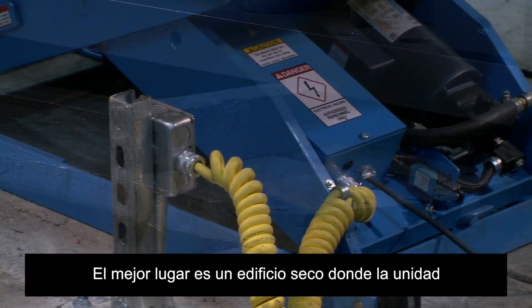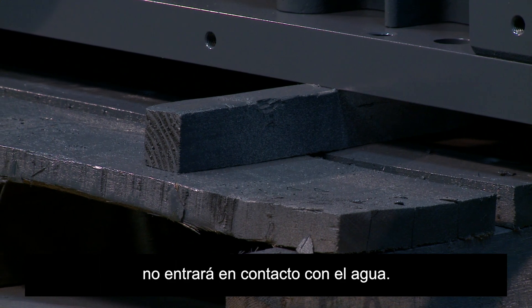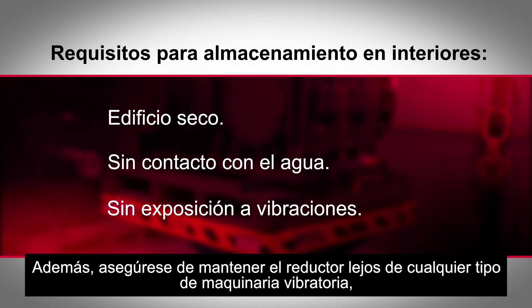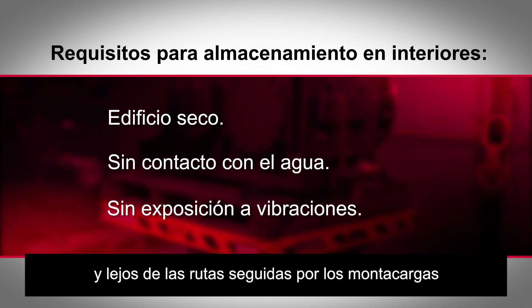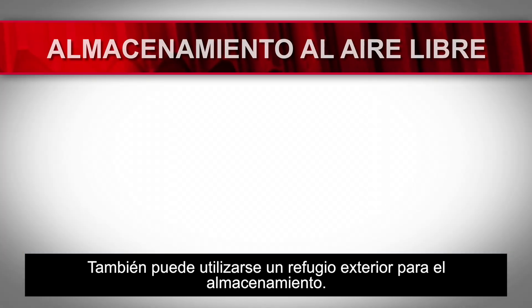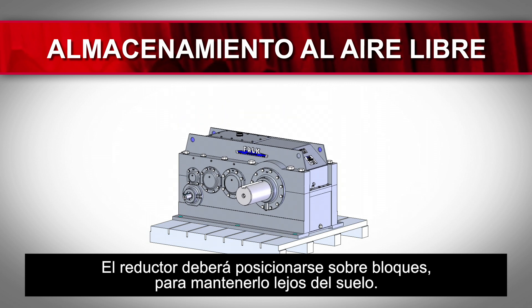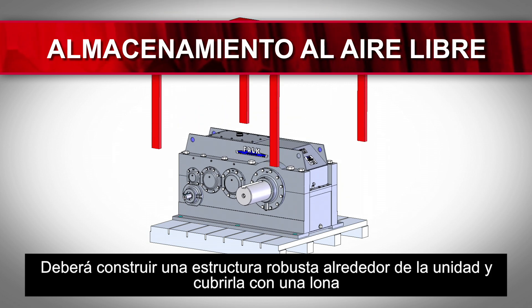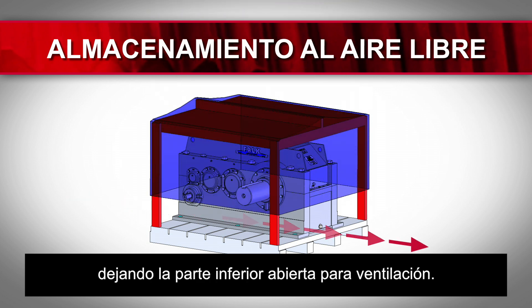It's important to keep the unit in an isolated spot when placing it into storage. The best place is a dry building where the drive will not come in contact with water. Be sure to keep the gearbox away from any form of vibrating machinery and away from the driving path of forklifts or similar equipment that could transmit vibrations to the stored unit. An outdoor shelter can also be used for storage. The gearbox should be positioned on blocks, keeping it off the ground, with a sturdy frame around the unit covered with a tarpaulin, leaving the bottom open for ventilation.